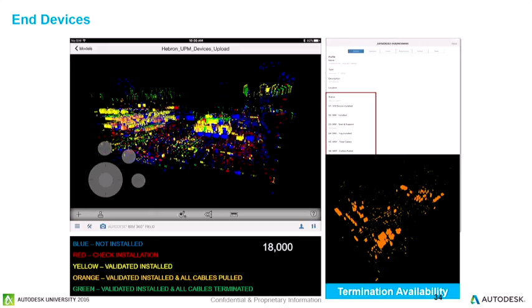So how do we take the data post-terminations? The terminations drove the ability to do megger checks on the cables, which enabled us to sign check sheets. We built the relationship: a panel has a power cable that feeds a junction box, an instrument cable that feeds a device. We knew the status through our MC system, using the data from BIM360, so when all these triggers go off, you can go shoot that loop.